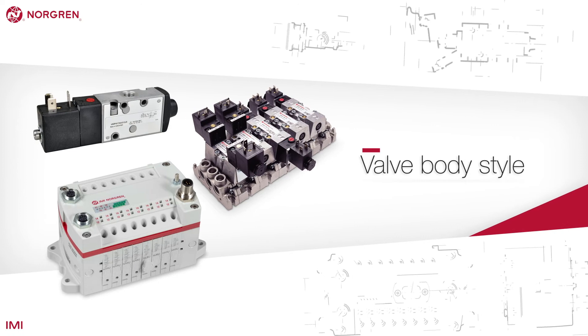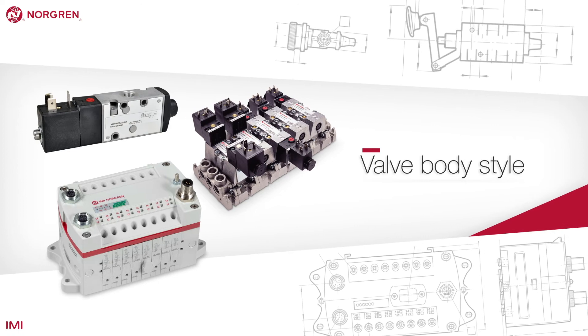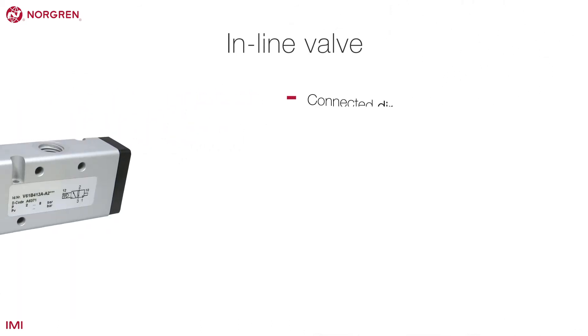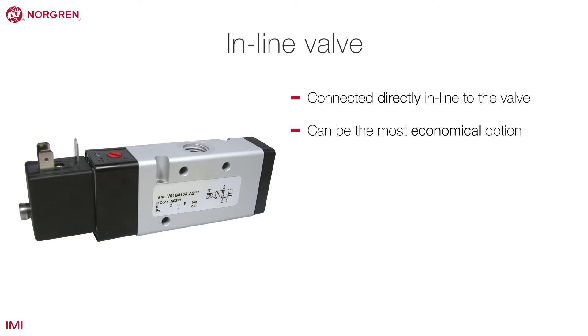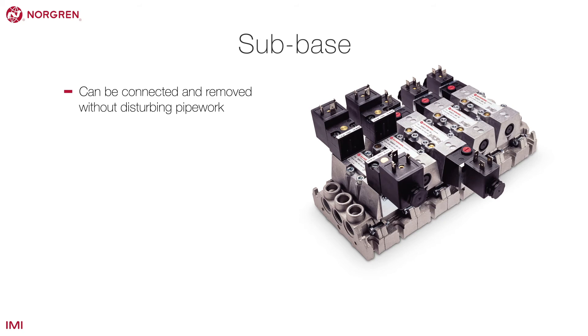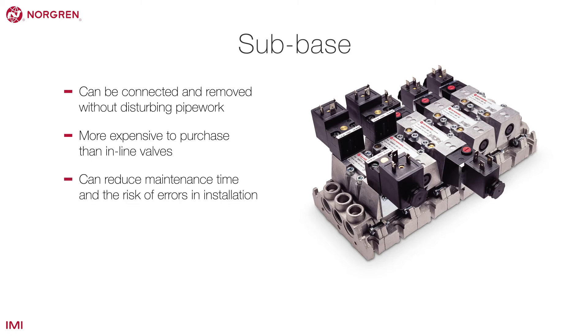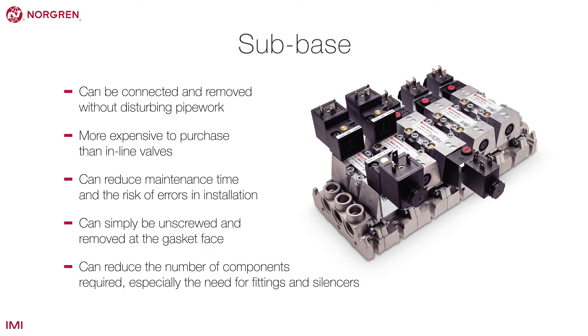The way in which a valve is attached to a system depends on the valve body style. The three most common styles are: inline, where the pipework is connected directly inline to the valve and can be the most economical option; manifold mounting of inline valves, which allows common supply and exhausts with working ports 2 and 4 connected individually; and sub-base, which allows valves to be connected and removed without disturbing pipework. Although more expensive to purchase than inline valves, sub-base valves can considerably reduce maintenance time and the risk of errors in installation, and drastically reduce the number of components required, especially fittings and silencers.